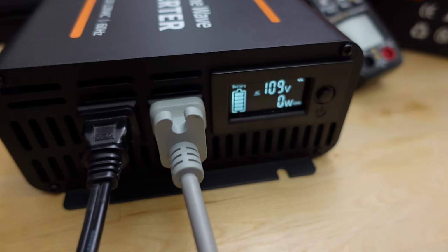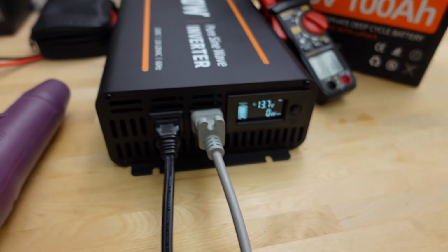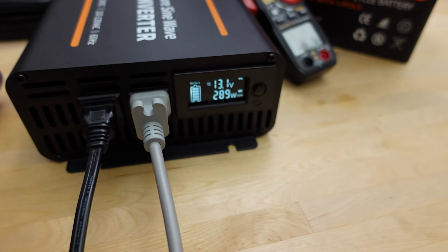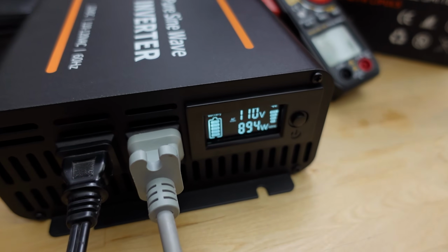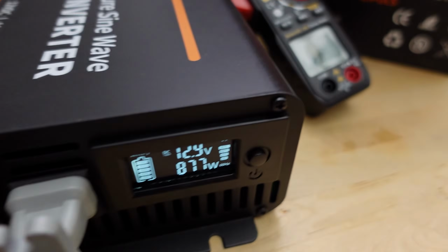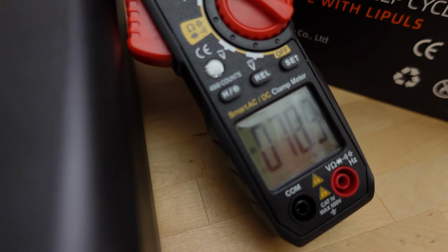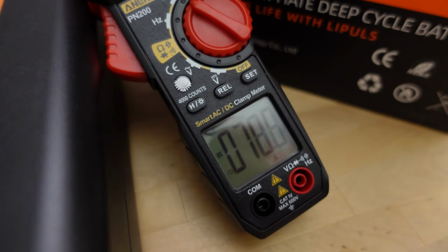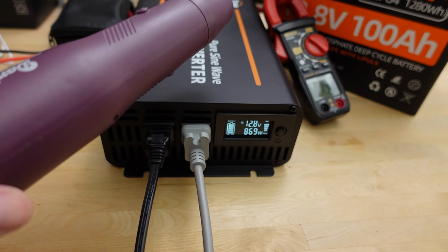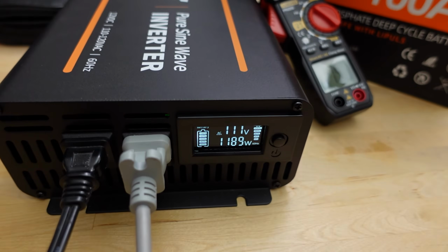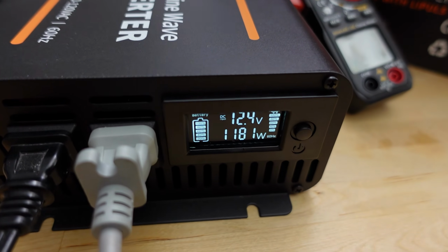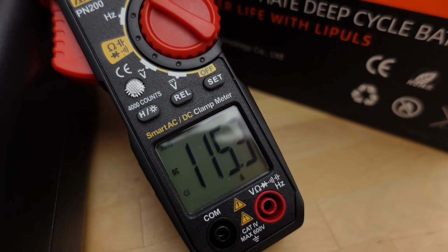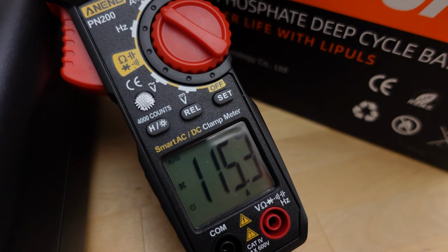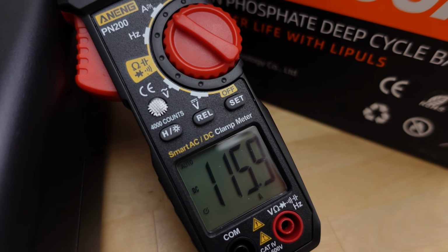On my maximum discharge test, I hooked this up to a 1,000 watt inverter, along with a vacuum cleaner and a heat gun. This is the most that I could hook it up to, I don't have anything larger. I was able to get it up to about 117 to 118 amps maximum discharge for a pretty long period of time. It's rated for 100 amps continuous, and it could probably do 118 amps for a fairly long period, maybe even for the whole capacity of the battery, although that's definitely not recommended or good for the battery.